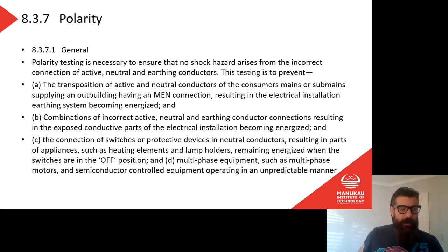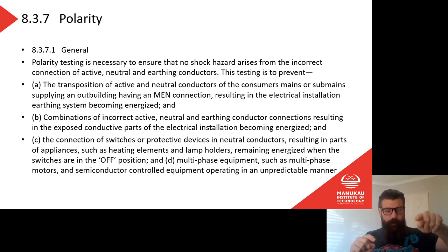So that means if you think about a light switch, I have a circuit running: phase wire, light switch, light, back to neutral. When I wire up my light switch, if I switch the live and the neutral, it will still work. I still have a circuit path, a switch, a light, and a return path. There's no issue there. Physically, in terms of its ability to work, if I turn the switch off, it's still going to break the circuit. If I turn the switch on, it's still going to allow the light bulb to go.